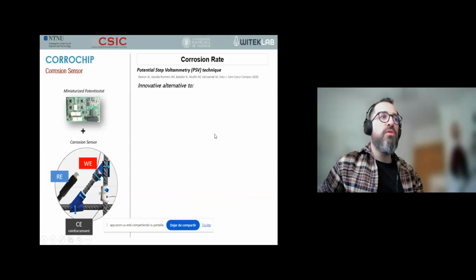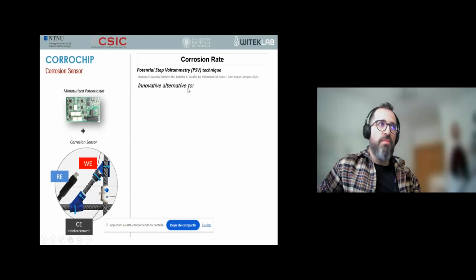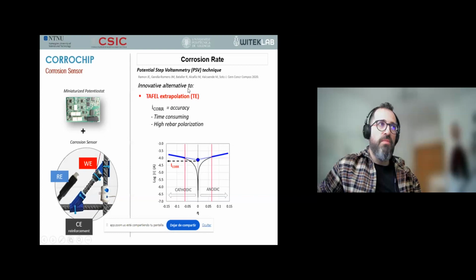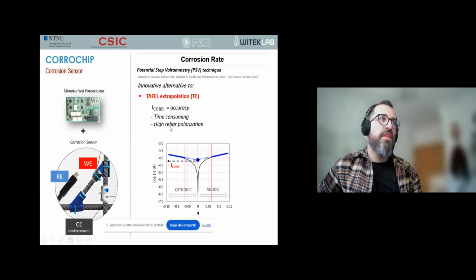As mentioned above, the Corrochip sensor uses a new polarization technique to determine the local corrosion rate. This is the potential step voltammetry technique, an innovative alternative to traditional methods. On the one hand, there is the Tafel extrapolation method, in which the corrosion rate is obtained by intersecting the linear regions that appear in the polarization curves obtained in response to wide potentiodynamic scans. It is an accurate technique. It has the disadvantage of being very slow and time-consuming, which can lead to high rebar polarizations, which can also lead to irreversible alterations of the rebar.